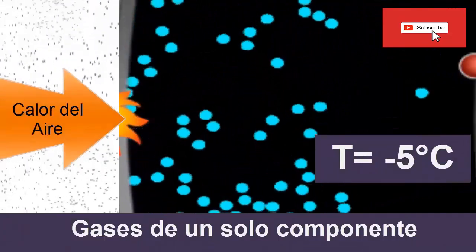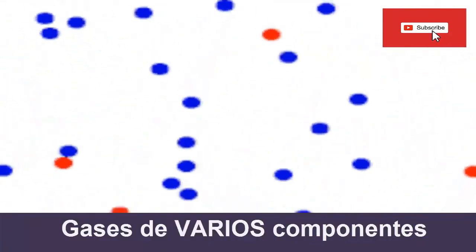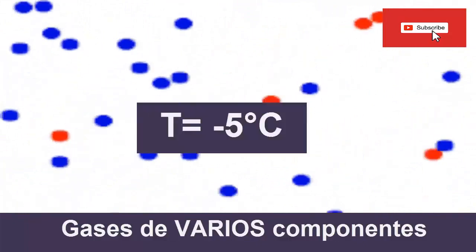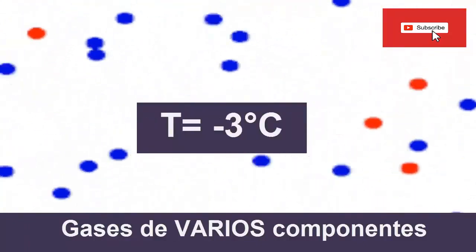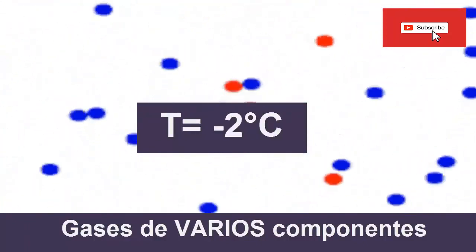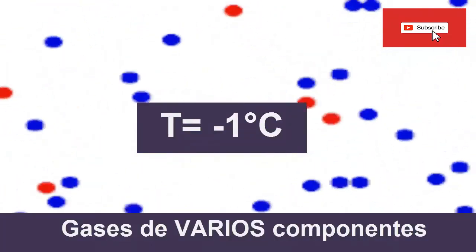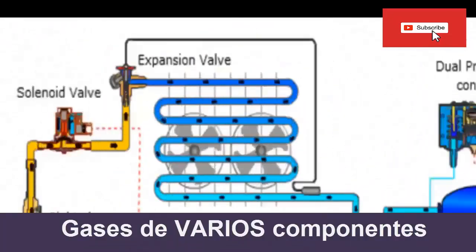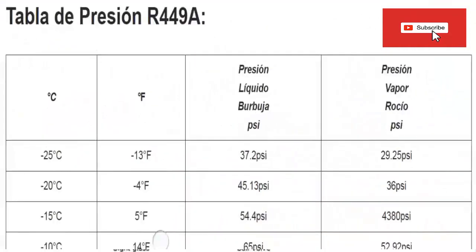However, there are refrigerants that are made from the mixture of several gases, where there can be a small increase in temperature while its phase change occurs. This phenomenon is called refrigerant glide. On the screen, we have the table of pressure and temperature of the refrigerant gas R449A. As we can see in the table, we have two pressure columns: one corresponds to vapor or dew pressure, and the other to liquid or bubble pressure. This occurs because R449A has glide.